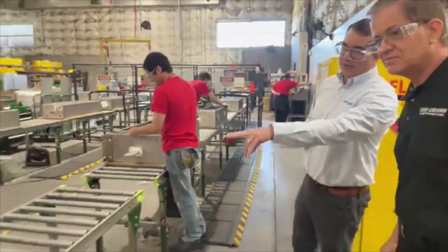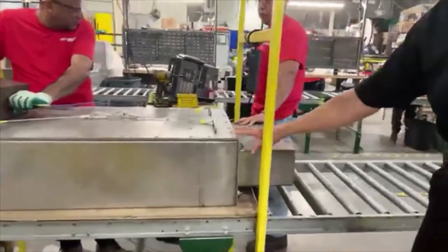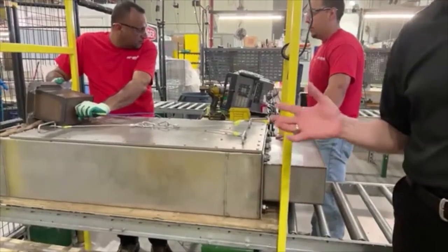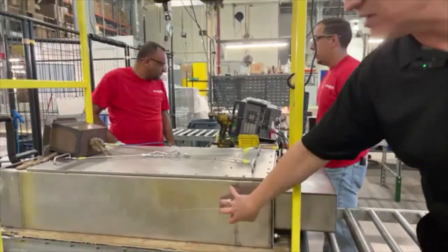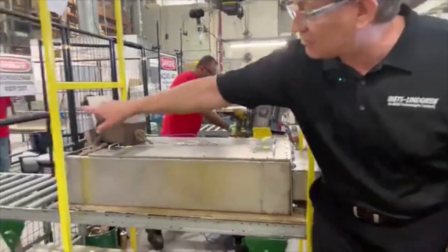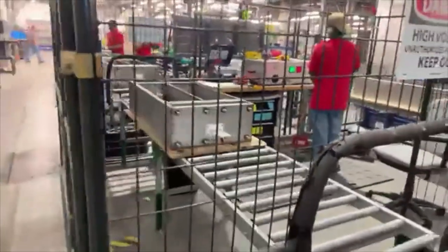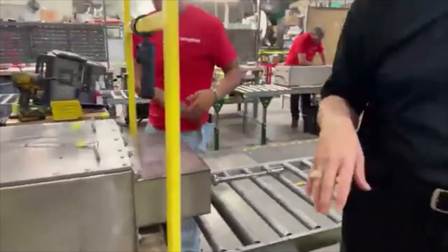This extension off here is simulating that the filter is inside the enclosure — the cabinet — because this is only a filter element and the bus bar terminals are exposed. What we need to do is simulate or isolate the input from the output so that we can do a good insertion loss test, which measures the attenuation of the filter. It's like a shielded cap on there — exactly, that's what this does.